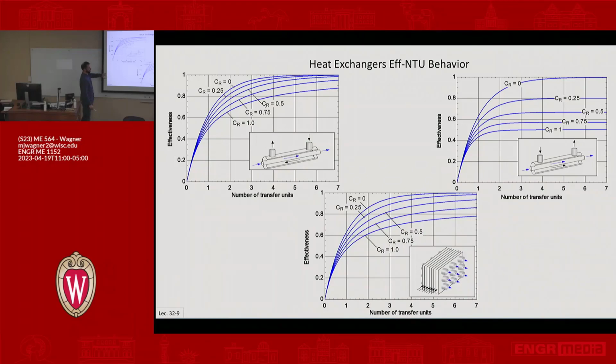The other thing to take away, to put in your brain: if you're doing a counterflow heat exchanger, NTU should always be, let's say, between 1 and 6 or 7. If you compute something and you have an NTU of like 50, you are paying way too much for that heat exchanger. It's not helping you, assuming it's not free.